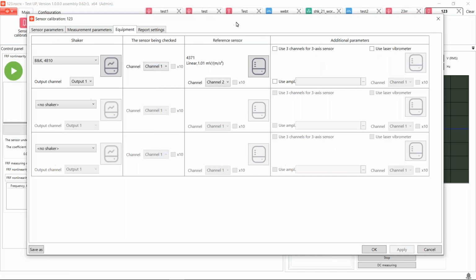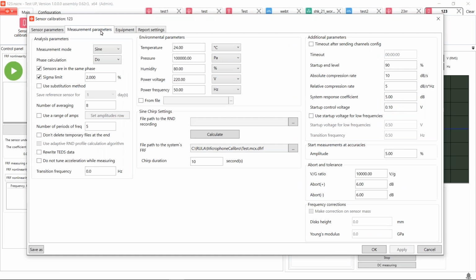Although back-to-back calibration is widely applied, it can be inaccurate if the sensor under calibration is bigger or heavier than the reference sensor. And to avoid such an error, in TestUp software, we implemented the procedure of calibration by substitution. This feature can be chosen in the measurement parameters, so you can just put a tick to use substitution method. And this method allows, of course, for maximum accuracy, but unfortunately it takes more time.